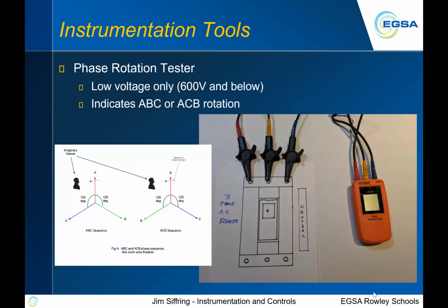So anyway, okay, next tool you might want to consider having if you're ever going to be commissioning UPSs, transfer switches, anything such as that, is a phase rotation tester. So what is that? It's just a device to tell you what your rotation is. Is it ABC or ACB? And that's a very important thing to look at, especially if you're commissioning transfer switches, where you're going to be switching from, say, a utility source to a generator source, or maybe from a generator to a generator. You want to make sure that your rotation is in the same direction.